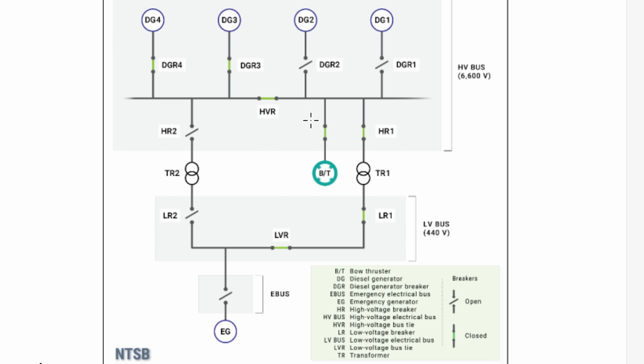Everything shuts off at this point. And by the design of this ship, when these shut off, the HR1 and the LR1 both open, which is why you lost power to the low voltage bus as well. So once again, the entire ship has no power.